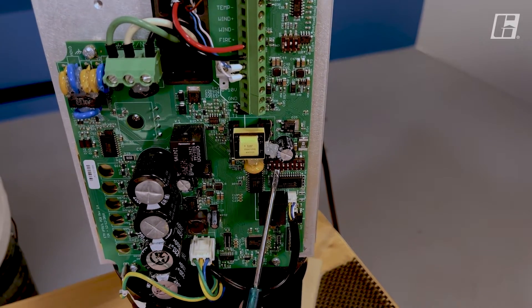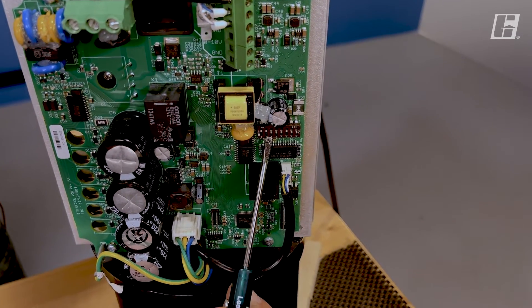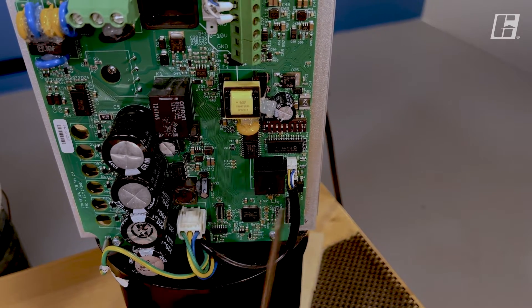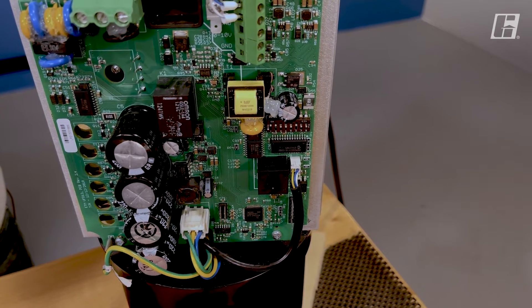Below that we have an addressing bank of dip switches. This needs to be independent for every fan that is connected within a network. Typically the first fan in the network is set for address number 2.